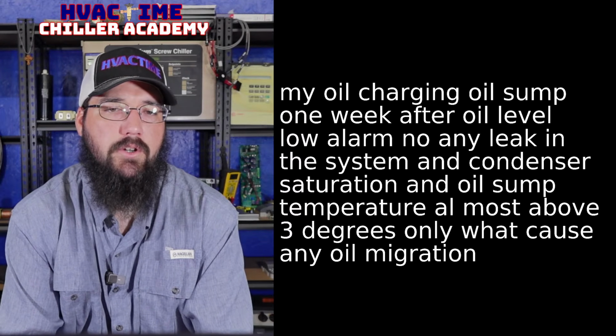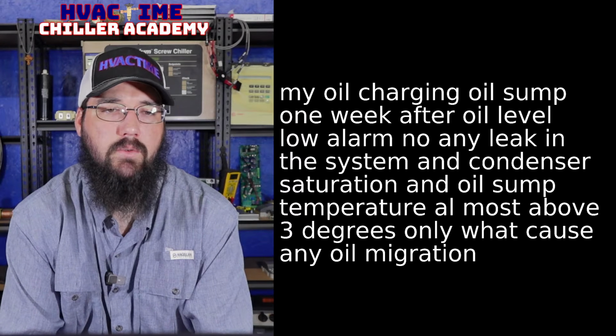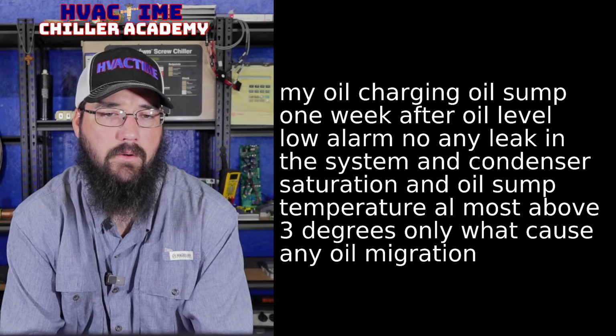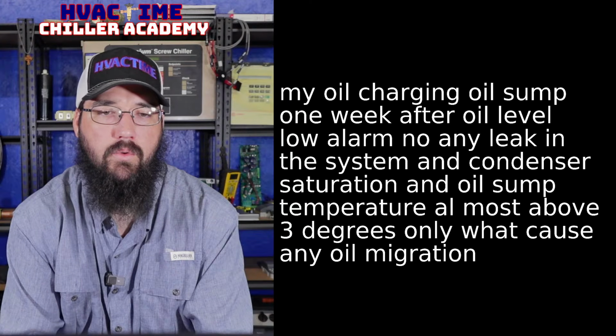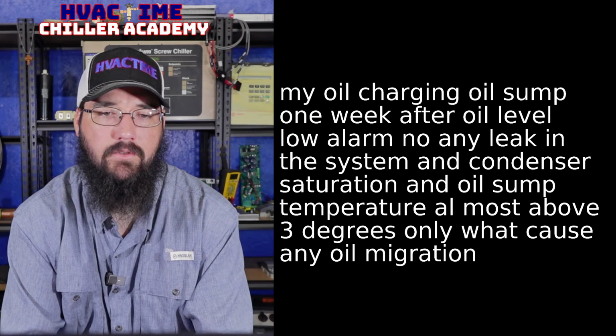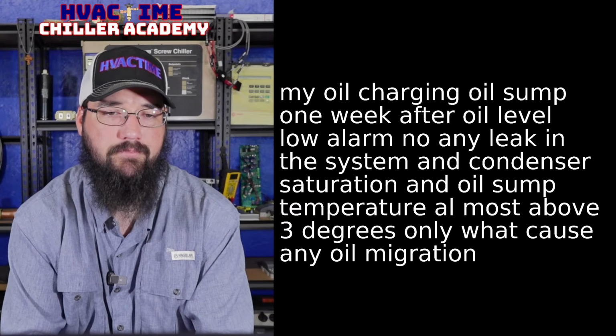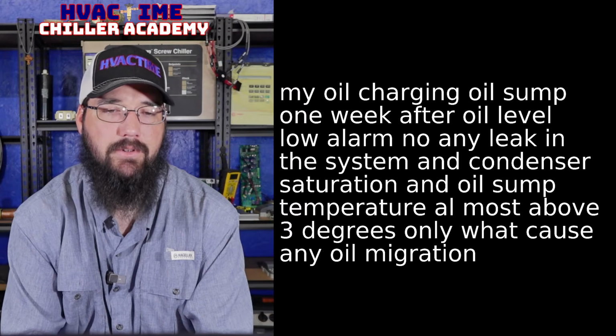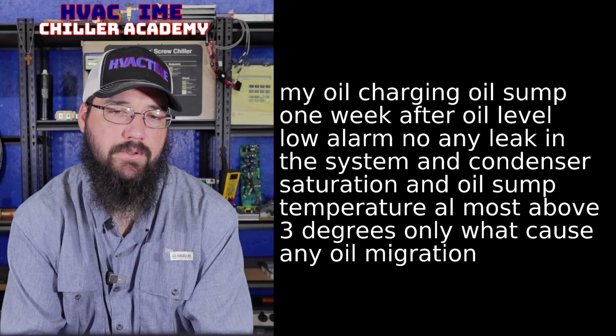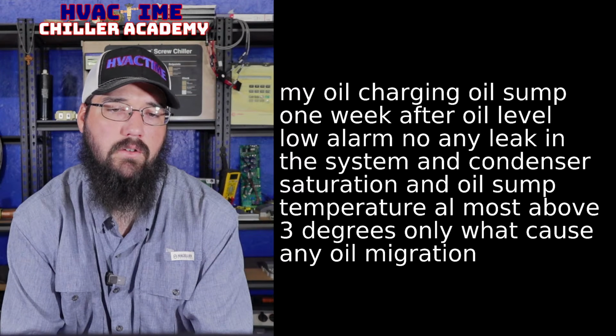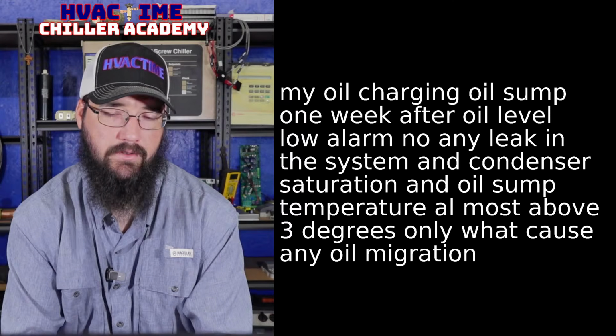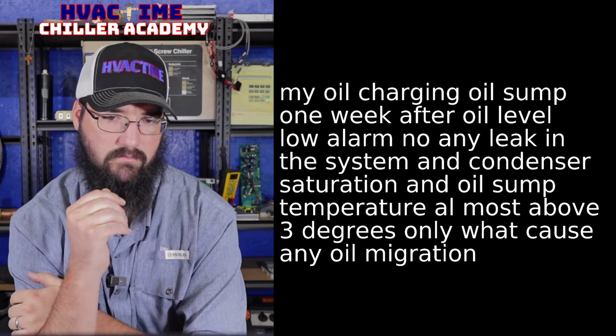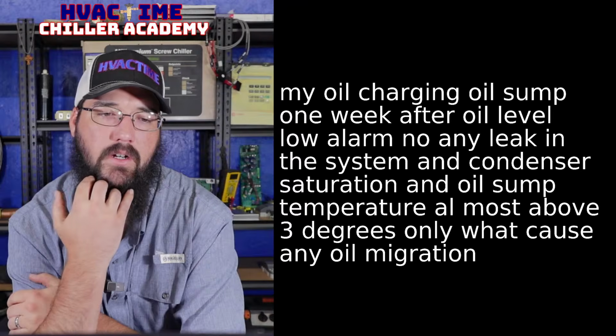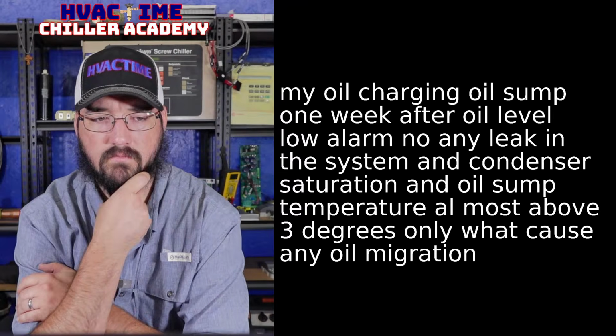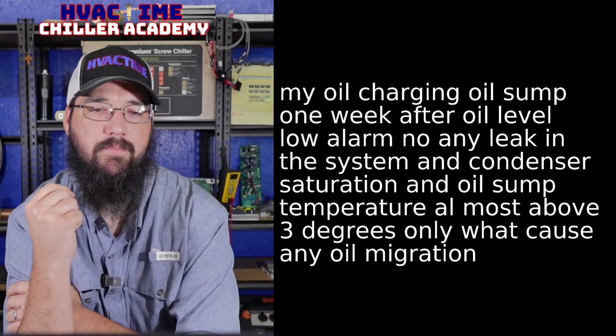My oil charging, oil sump one week after oil level low alarm, no leak, so no leak at all in the system, and condenser saturation and oil sump temperatures all almost above 3 degrees. Only what cause any oil migration?